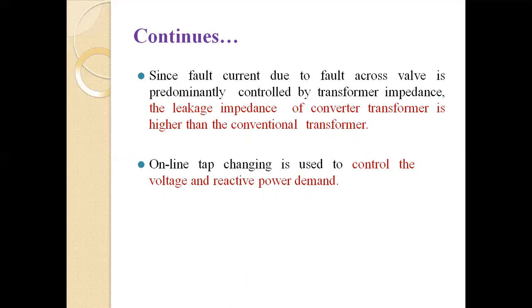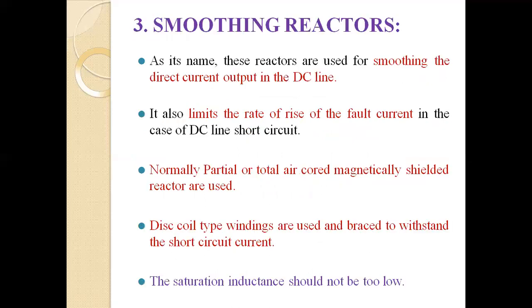On-line tap changing is used to control the voltage and the reactive power demand. Next part is the smoothing reactor. As its name suggests, this reactor is used for smoothing the direct current output in the DC line. It also limits the rate of rise of fault current in the case of DC line short circuit.